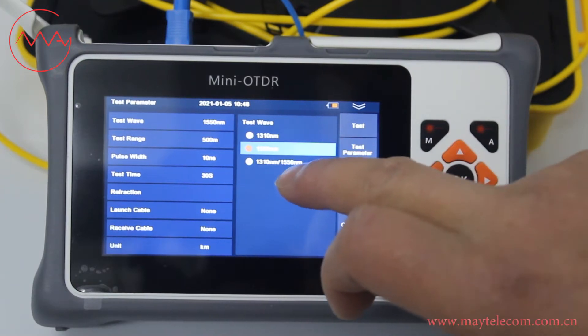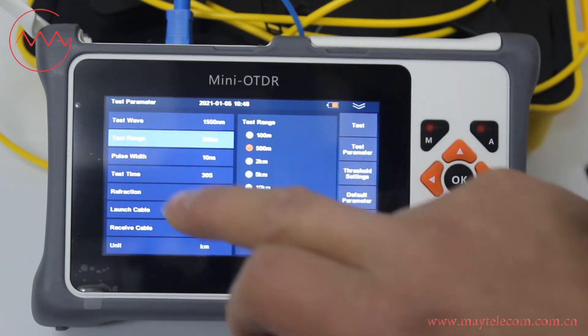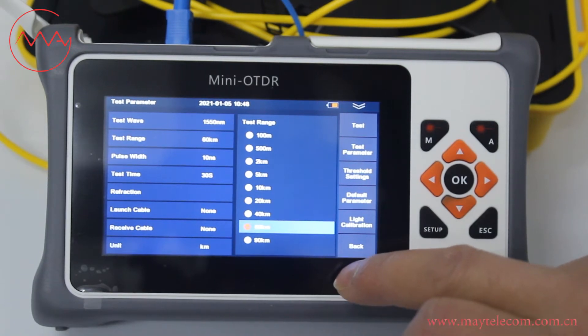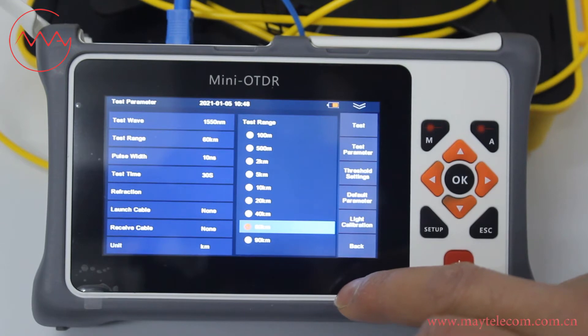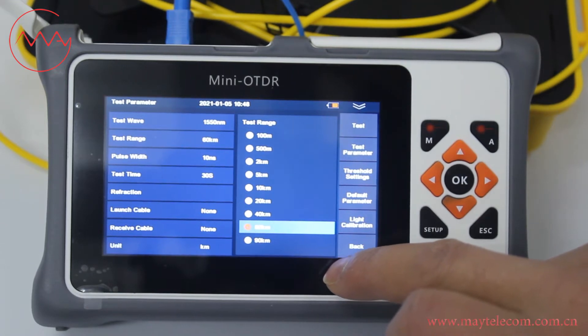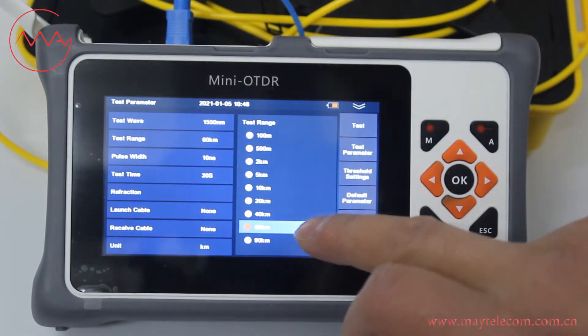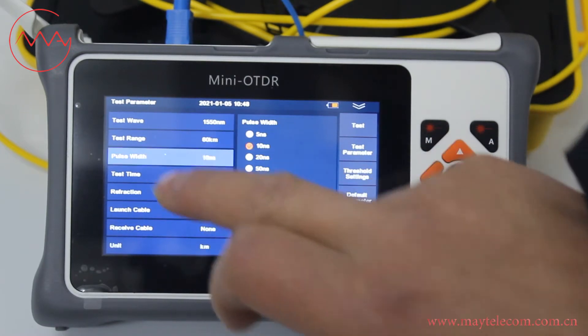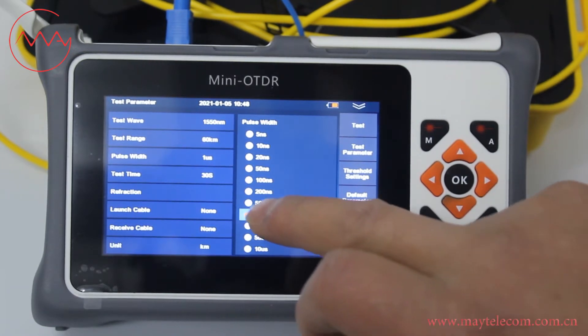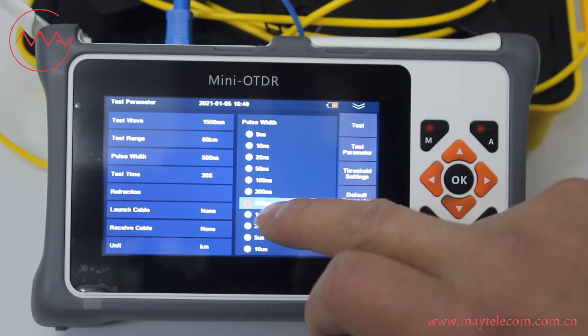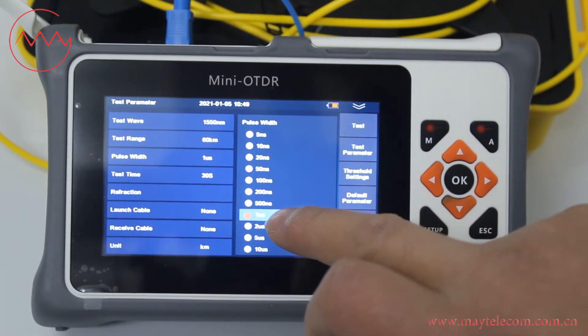Select 1550 for example. For test range, select 60 kilometers. The total length of 5 spools is around 30 kilometers. The test range is two times the total length of the 5 spools. For pulse width, select 1 microsecond or 500 nanoseconds. We select 1 microsecond for example, because the test range is 60.